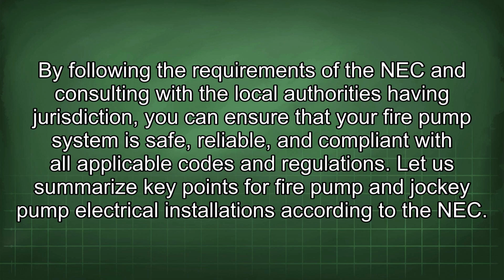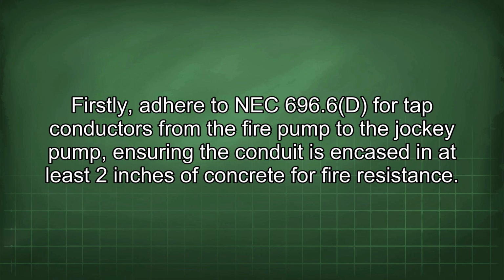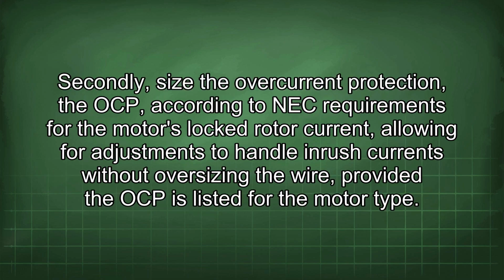Let us summarize key points for fire pump and jockey pump electrical installations according to the NEC. Firstly, adhere to NEC 695.6(D) for tap conductors from the fire pump to the jockey pump, ensuring the conduit is encased in at least 2 inches of concrete for fire resistance. Secondly, size the overcurrent protection, the OCP, according to NEC requirements for the motor's locked rotor current, allowing for adjustments to handle inrush current without oversizing the wire, provided the OCP is listed for the motor type.